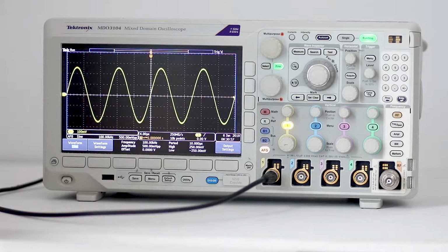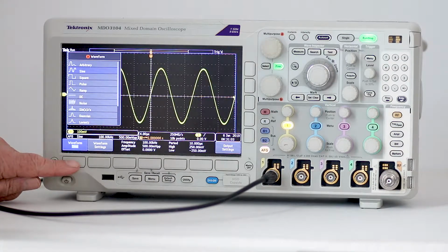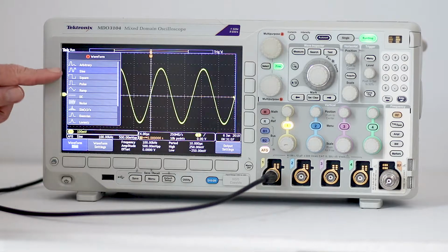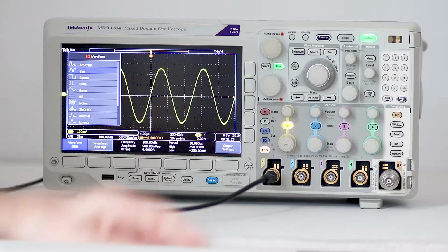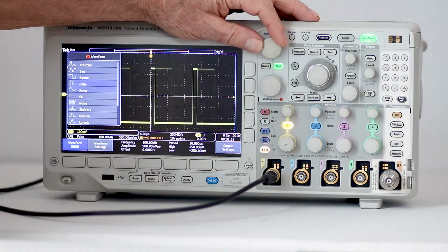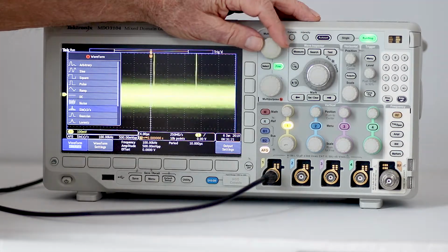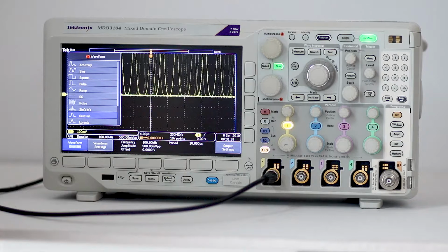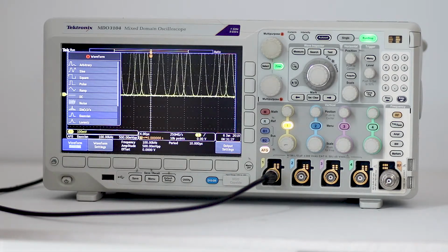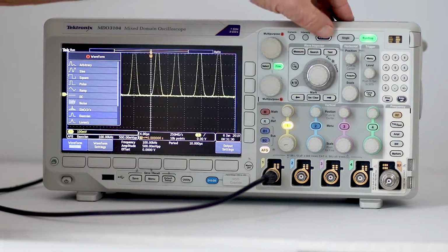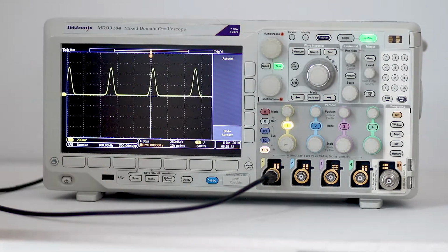Pressing the soft key associated with waveform, we see a list of the available internal waveforms. Sine wave is highlighted. Multipurpose knob A scrolls through them. For some waveforms, such as Gaussian, you have to press auto set because they have unique triggering and/or amplitude levels. Then, returning, let us say, to square wave or sine wave, you may have to press AFG once more to get back to the AFG menu.